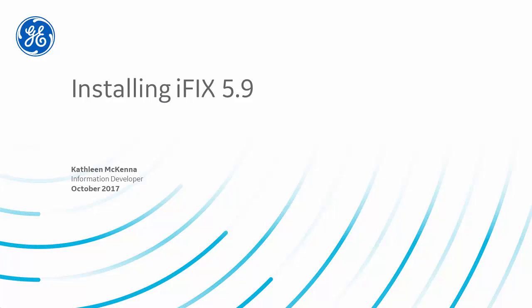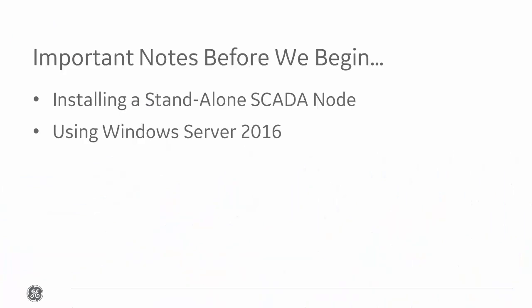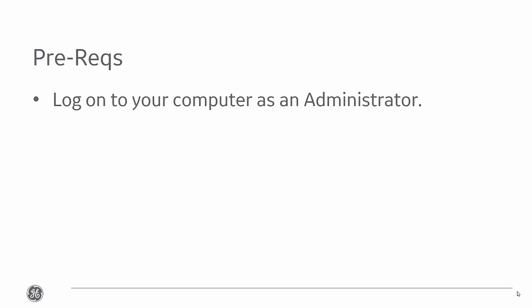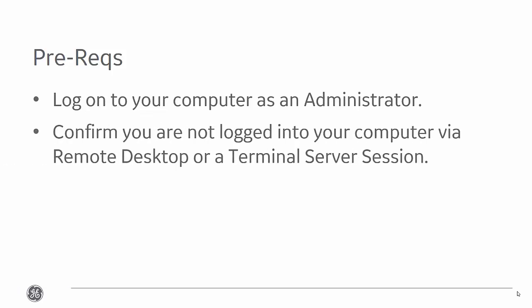A few important things before we get started. iFix is supported on several Windows operating systems, but for this video we'll be installing a standalone iFix SCADA node on Windows Server 2016. For a complete list of supported operating systems, just Google 'iFix software requirements' to get the latest list from our eBooks. Before you begin, log into your computer as an administrator, confirm you aren't logged in via an RDP or terminal server session, and make sure there are no other GE processes running.